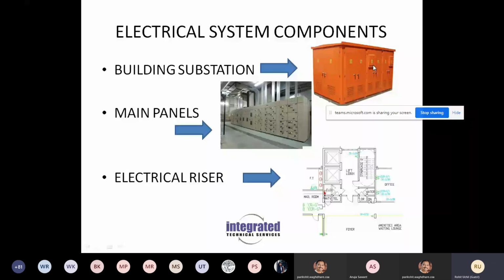Once you step it down in the substation, the power is passed on to these panels. These panels are most often in the basement of a building, and from there it goes through these rising ducts, through which the cables are taken to something called an electrical riser. In this case, I've just put in a small image of a drawing of a typical building core, which has a couple of elevators, a staircase, a lobby, and these shafts. So the electrical riser comes up through these electrical shafts.